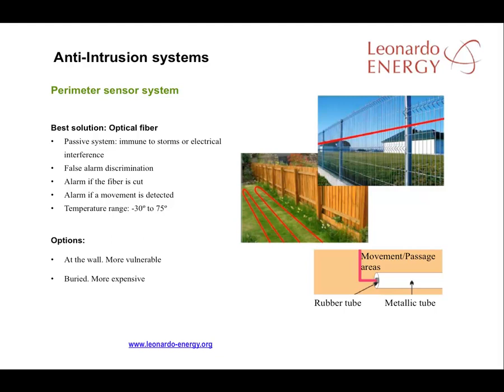There are a number of anti-intruder systems on the market, but the most important ones are the perimeter sensor systems and the presence sensors. Perimeter sensor systems activate an alarm if movement is detected at the boundaries of the PV facility. These sensors can be installed on the fence, which may be more vulnerable, or buried underground, which is better but also more expensive. The best solutions on the market use optical fiber — they are unaffected by storms or electrical systems and can withstand great temperature changes. They can discriminate between false and genuine alarms, or detect if the fiber has been cut. At the bottom right of the slide, you can see the recommended method for installing these systems.